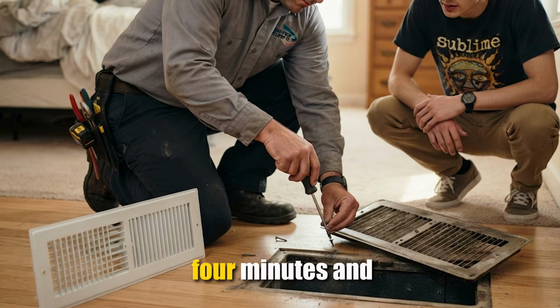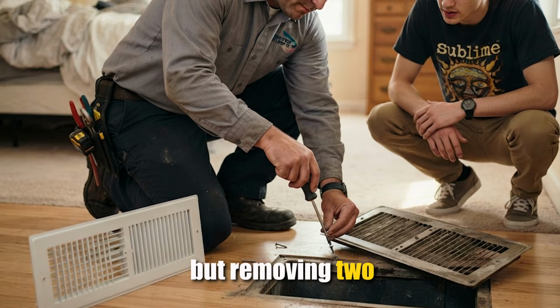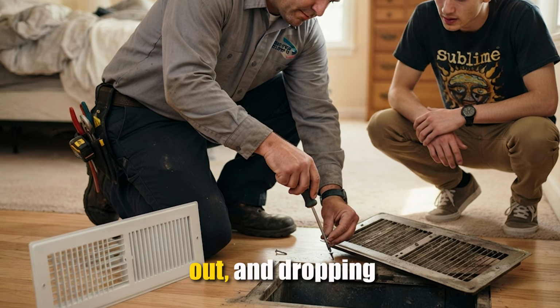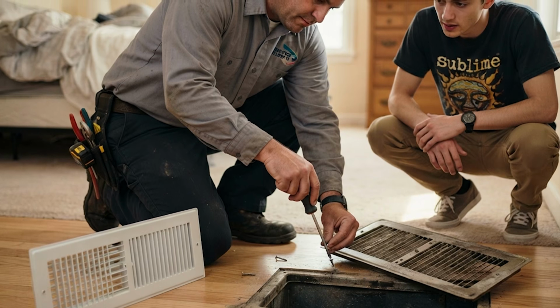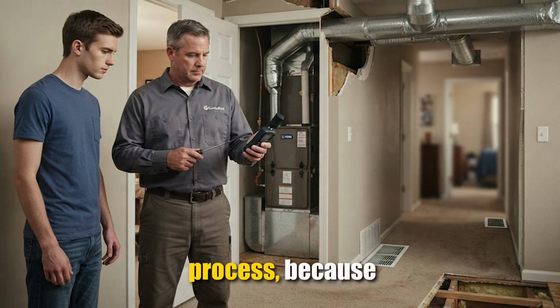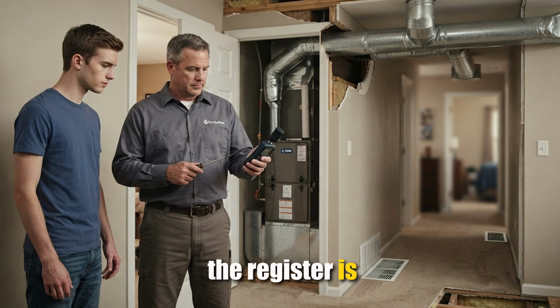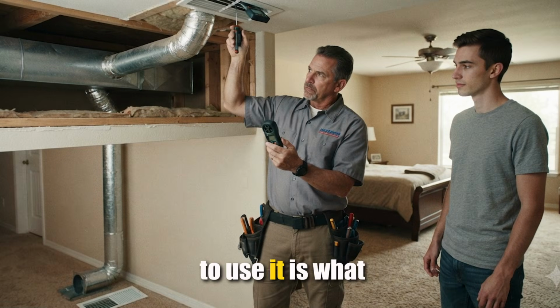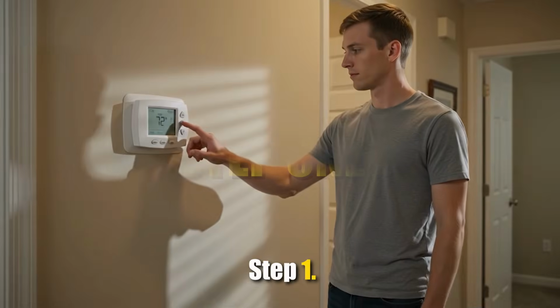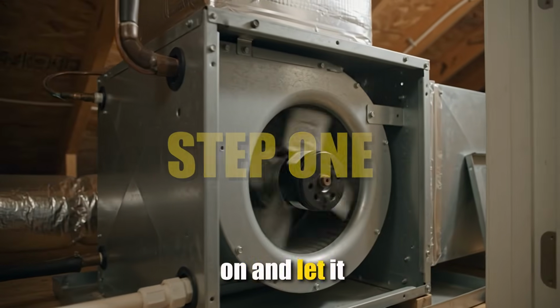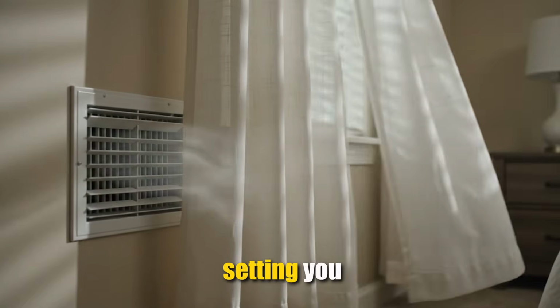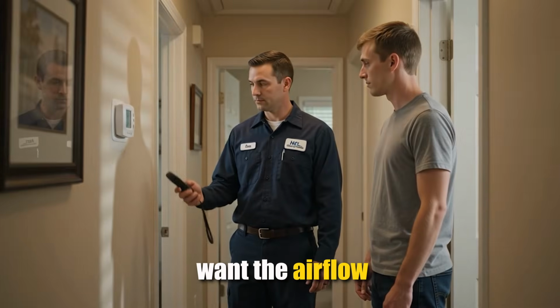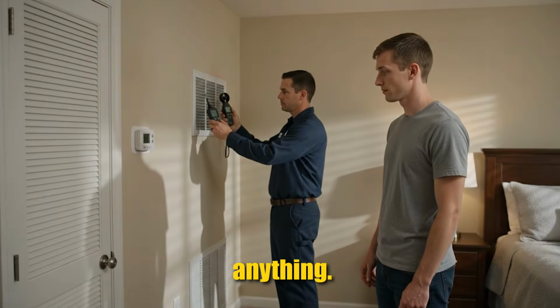The installation is 4 minutes and requires nothing but removing 2 screws, pulling the old register out, and dropping the new one in. Now let me show you the complete balancing process, because the register is the tool, but knowing how to use it is what produces the result. Step 1. Turn your system on and let it run for 20 minutes at the thermostat setting you normally use. You want the airflow to stabilize before you start measuring anything.